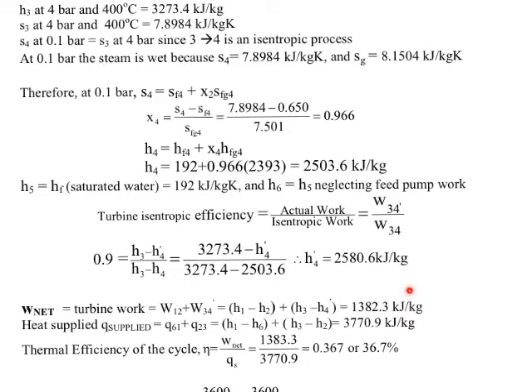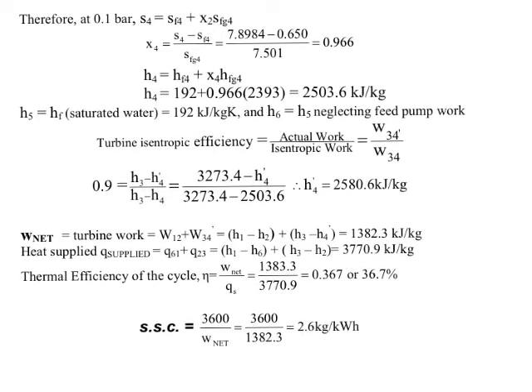The final calculation for the specific steam consumption is 3600 divided by our W net, which is 2.6 kilograms of steam needed per kilowatt-hour. An even more compact plant. But unfortunately, more complicated. This ends example 2.